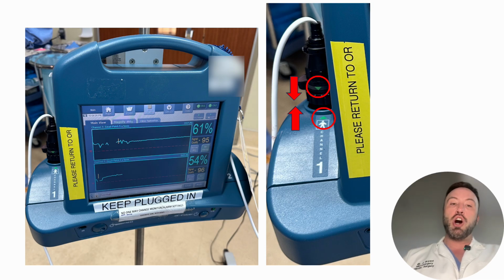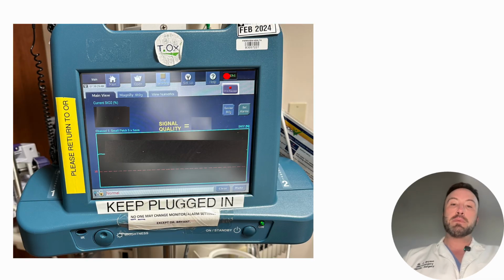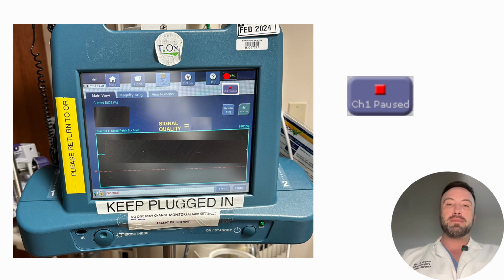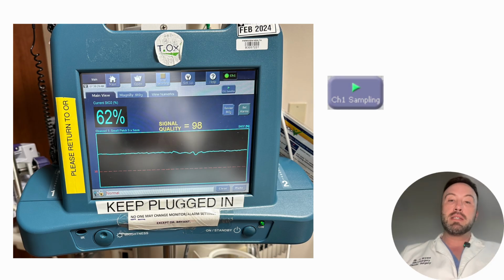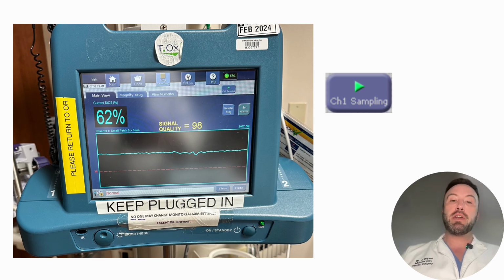Align the green arrows on the sensor head with the green arrows on the monitor channel. Do not push or force the sensor head. Instead, rotate the ring attachment on the sensor head clockwise until it snaps securely into place. Now that the ViOptix probe has been connected, tissue oximetry monitoring is begun by pressing the red square paused button on the monitor. This red box will change to a green arrow labeled sampling, indicating that the probe has begun monitoring.